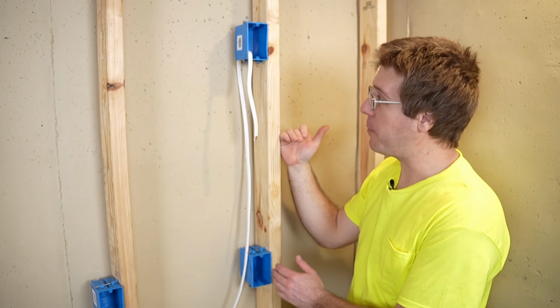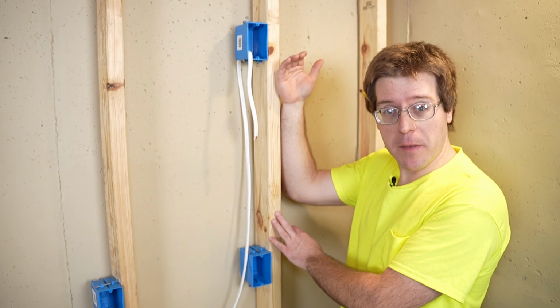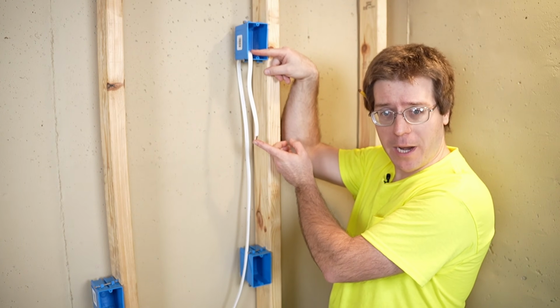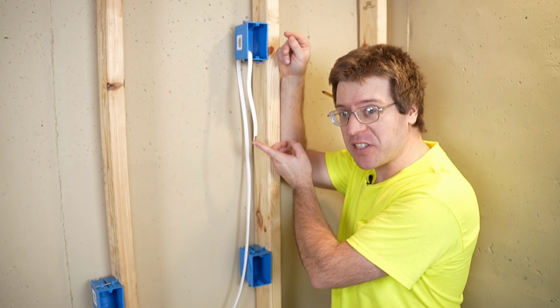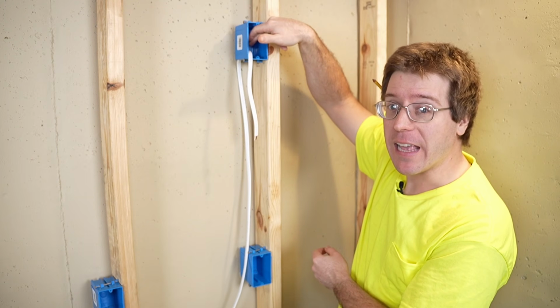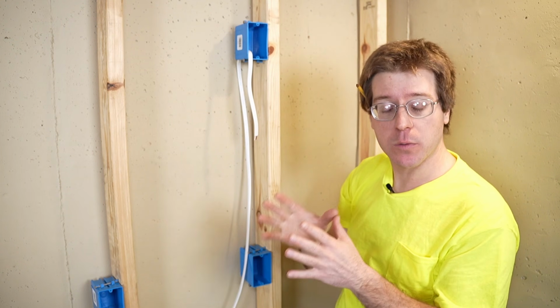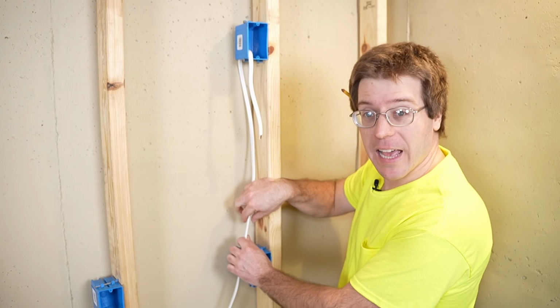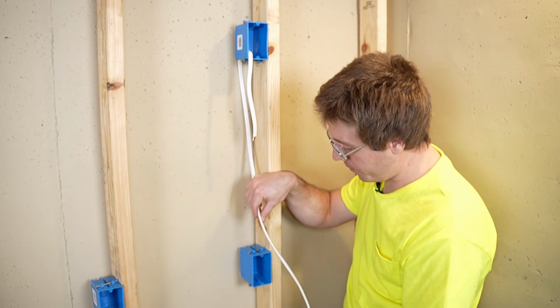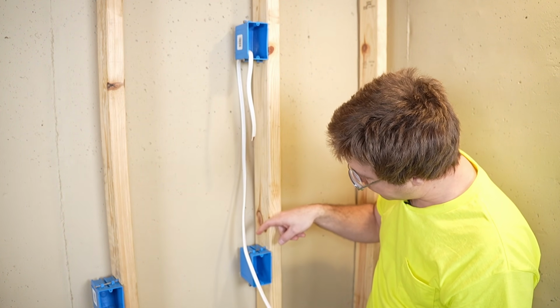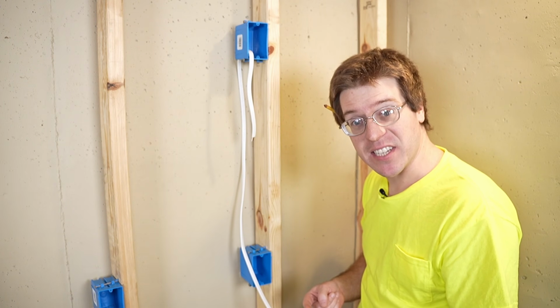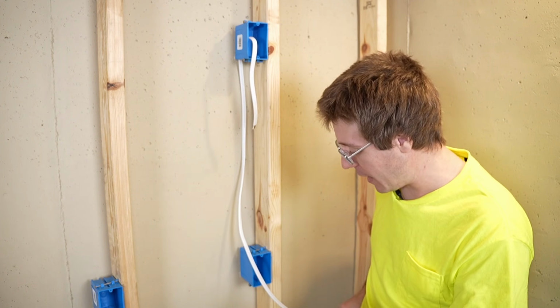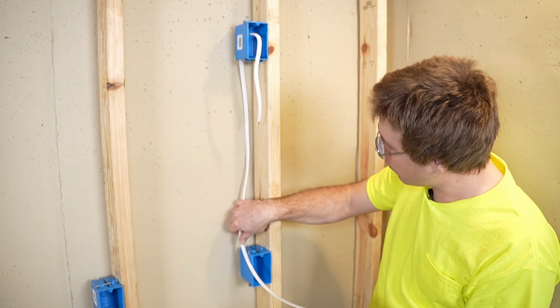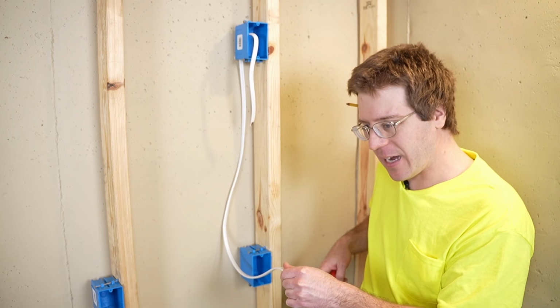Here's what this looks like big picture. We've got our wire just put into the box roughly, with more than enough sticking out. Remember, we need at least 6 inches of wire from where it enters the box available—that's one of the codes in our NEC. So we can pull a little more wire through and cut it, making sure we have enough to get into this box and still have at least 6 inches sticking out of this lower box. Holding it roughly right here, we'll go ahead and cut it.